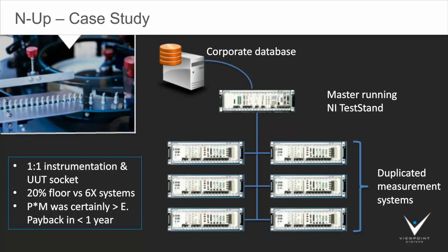Analysis using the equation from the earlier slide showed that a 6-up tester allowed the test operator to cover the test time with the load and unload time, so n in that equation was 6. Also, at the high volumes they needed, they had to parallelize as much as possible. The cost of 6 sets of test equipment and device sockets was less important than speed.